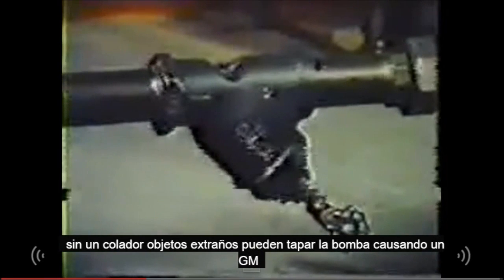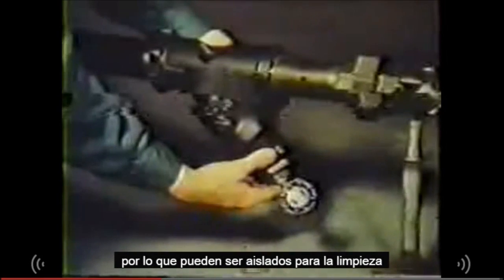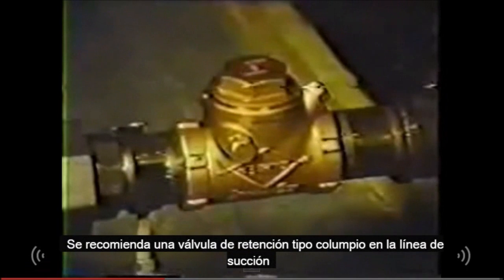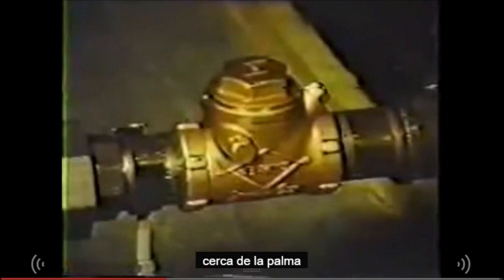It is always good practice to consider a strainer on the suction side of a rotary gear pump. Without a strainer, foreign objects could be drawn into the pump, causing a jammed pump, a broken part, or a torn-up drive. Provision should be made for cleaning the strainer. If the pump is to operate continuously, a bypass should be built around the strainer, or two strainers should be put in parallel with proper valving so they can be isolated for cleaning. A swing-type check valve is recommended in the suction line close to the pump.